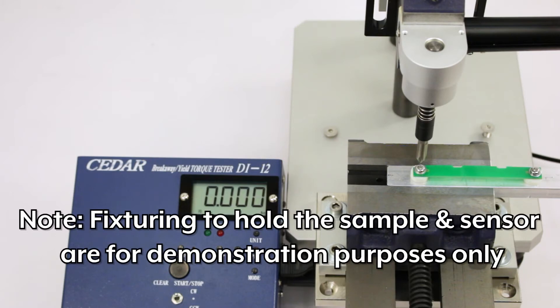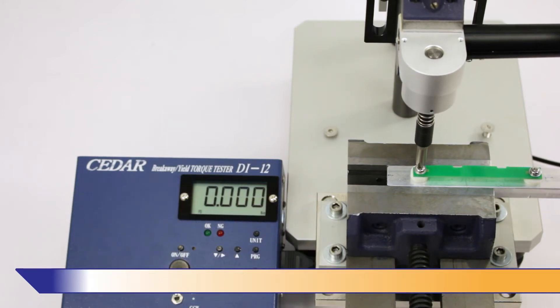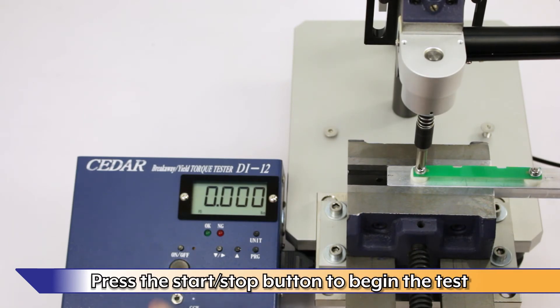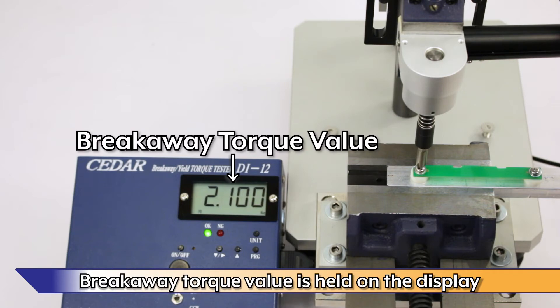Note, fixturing to hold the sample and sensor are for demonstration purposes only. Engage the sensor and fastener. Press the Start-Stop button to begin the test. Since the fastener is already tightened, the tester will instantly detect breakaway torque and stop. The breakaway torque value is held on the display.